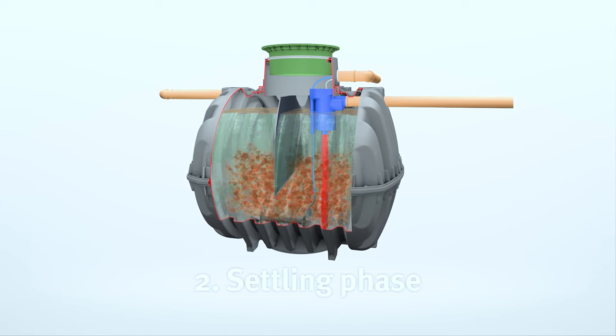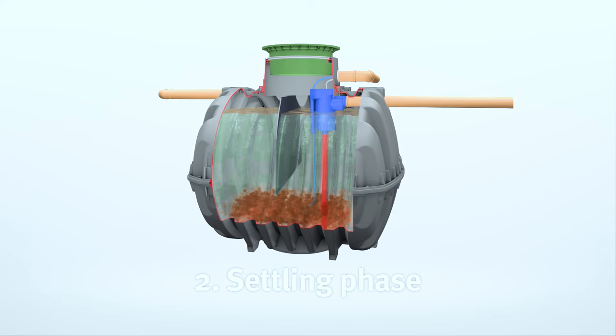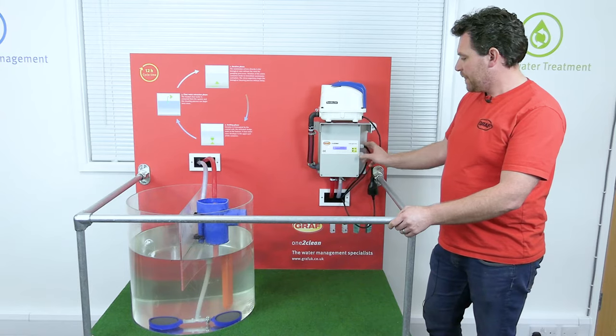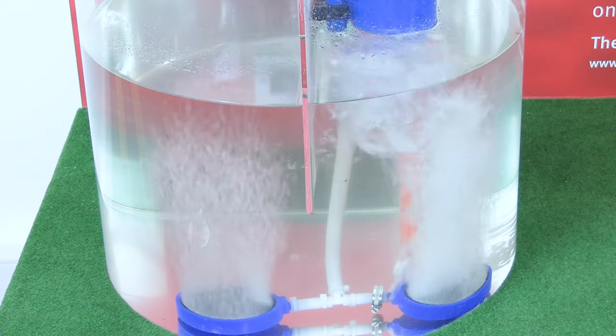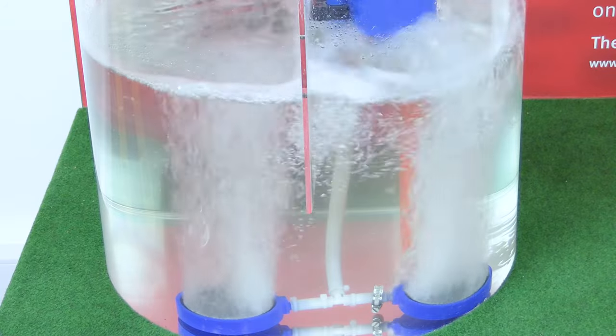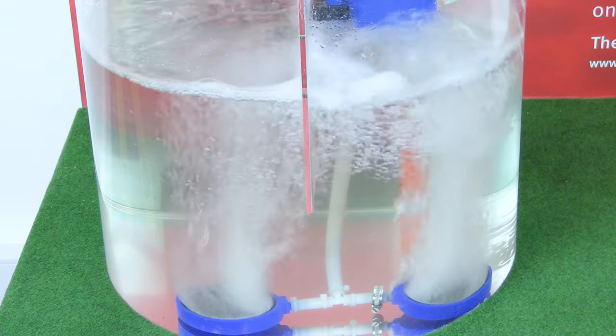With a Graf UK system, for the treatment of the waste we use SBR technology — for example in the One2Clean. In the secondary chamber of the One2Clean system, we introduce oxygen into the tank via an air diffuser which sits at the bottom of the wastewater tank. The diffuser helps to keep the bacteria that naturally grows in the waste alive by periodically giving the bacteria a supply of oxygen.